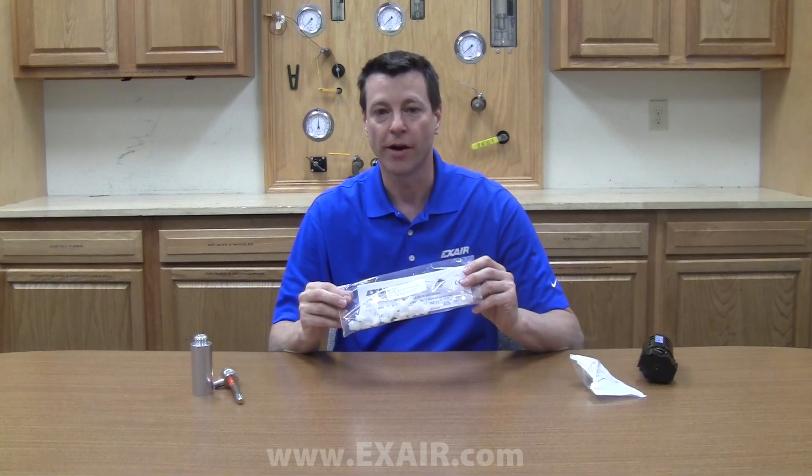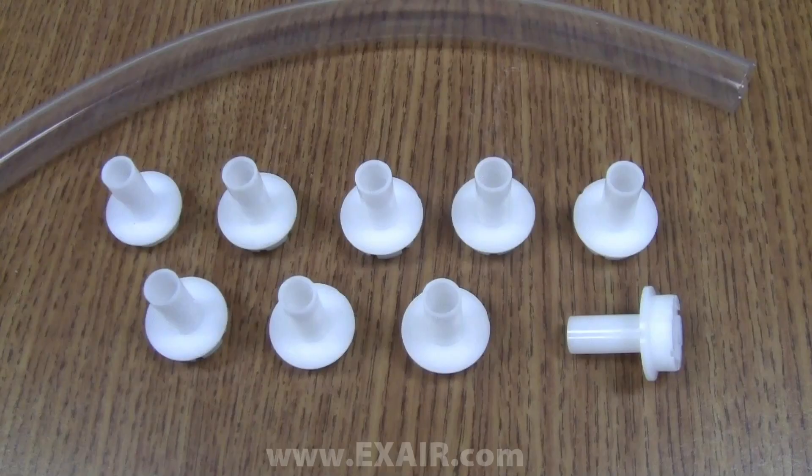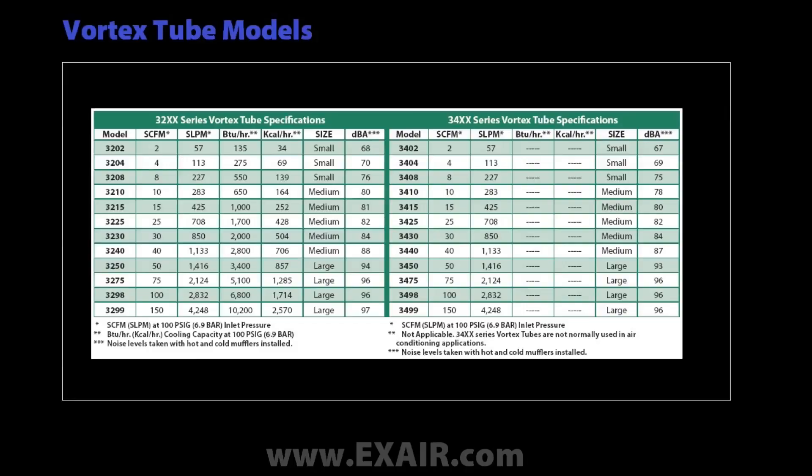Within the generator and small parts kit are nine generators. Generators are classified as either R style or C style. EXAIR offers two series of vortex tubes: the 3200 series, which provides maximum cooling power and uses R style generators, and the 3400 series, which provides the lowest cold air temperatures and uses C style generators. By installing any of the nine generators, in addition to the generator that comes pre-installed, it is possible to build each of the 10 medium vortex tube configurations that EXAIR offers.